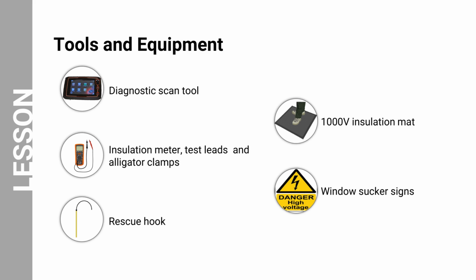Alligator clamps provide a temporary connection between the test leads and the vehicle's high-voltage system. They are useful when probing for test points or when the tested component lacks dedicated connector points. A rescue hook allows for the safe extraction of a person who might be experiencing electrical shock from a high-voltage component. A 1000-volt insulating mat provides a safe working surface to stand on while performing the isolation fault test. Window sucker signs can be placed on the vehicle to alert others of work being performed on a high-voltage system. Always remember to consult your manufacturer's recommendations for the components you are testing to determine the required test voltage.